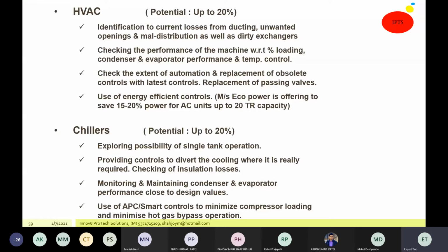And nowadays APC and smart control are used to minimize the chiller compressor loading and minimize the hot gas bypass operation. This is one of the areas where the engineer can look into it at the time of design itself, so that your energy consumption can be minimized.